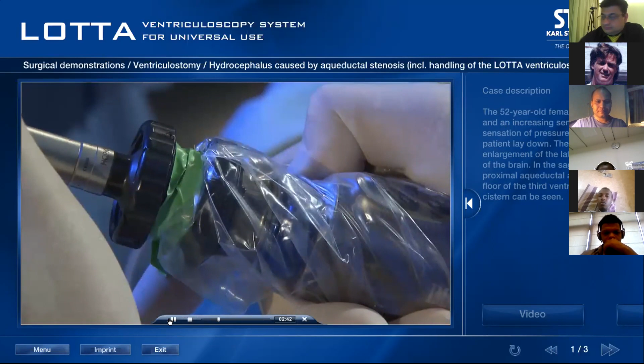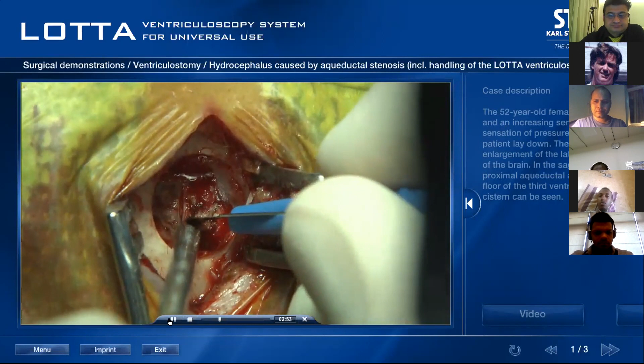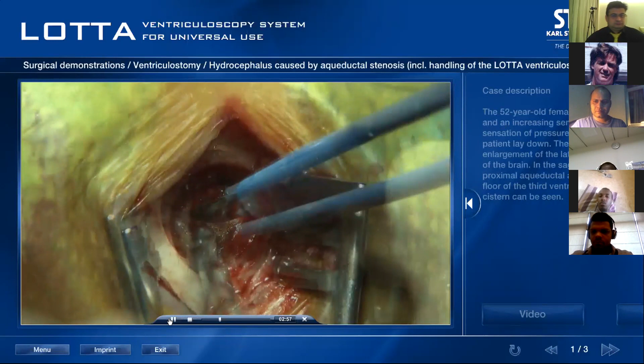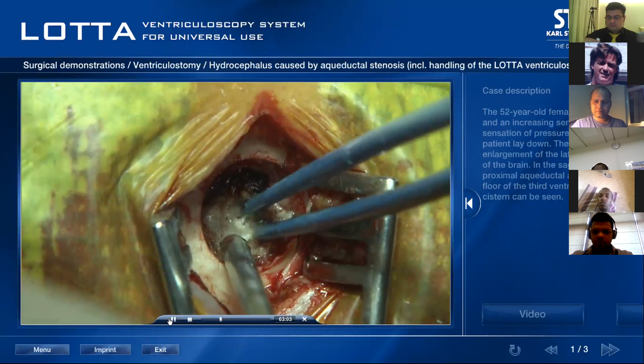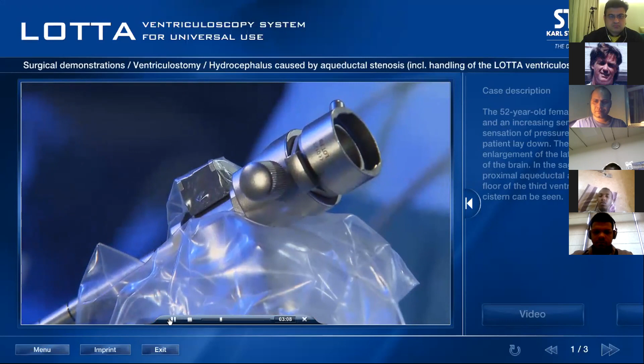Now, we move further and I explain. For the white balance, the focus and zoom are set using the small wheels on the camera head. After bipolar coagulation of the dura, a cross-shaped dura incision is made. This is followed by bipolar coagulation of the cortex. Once the endoscope sheath has been fixed to the pneumatic holding arm, the locking mechanism is locked.